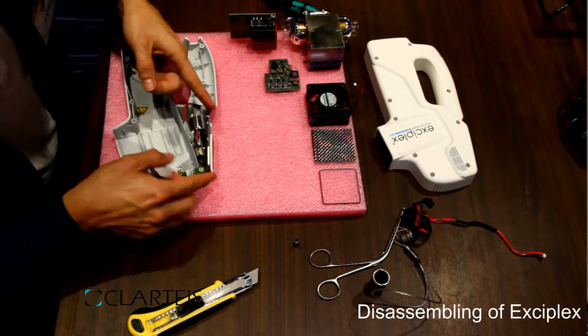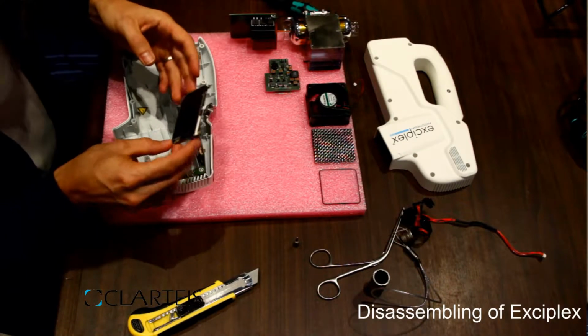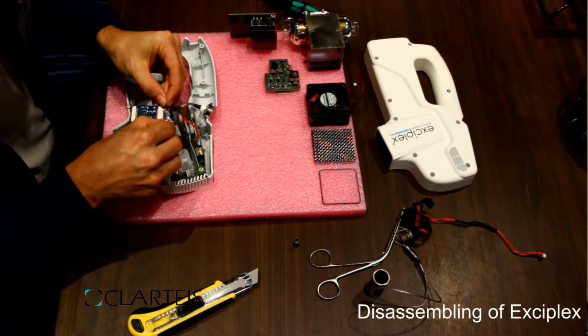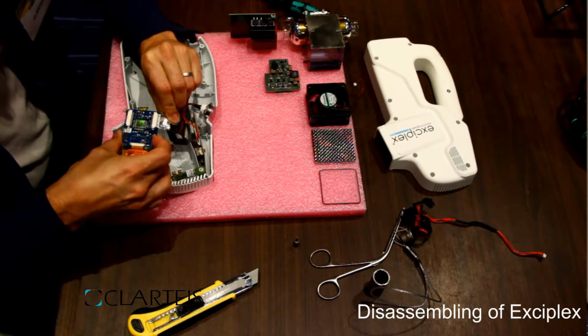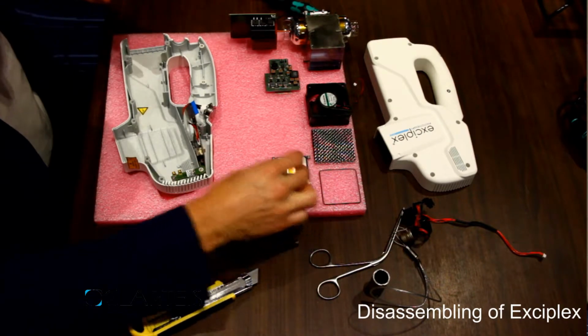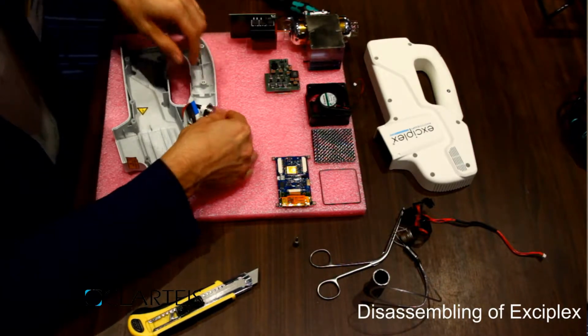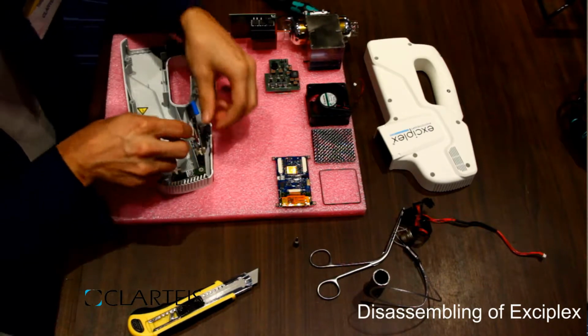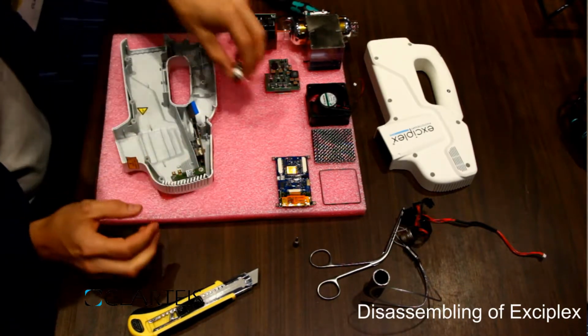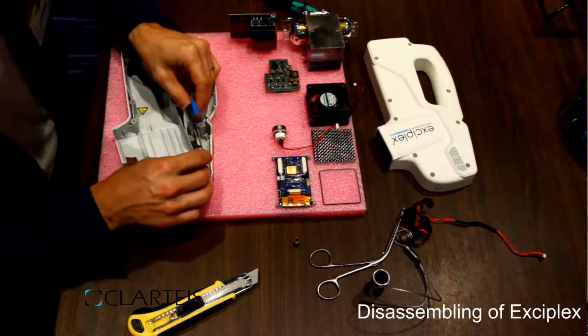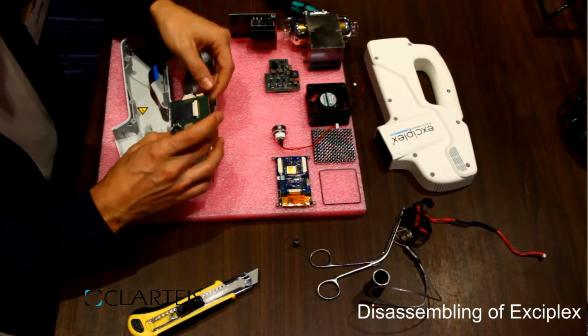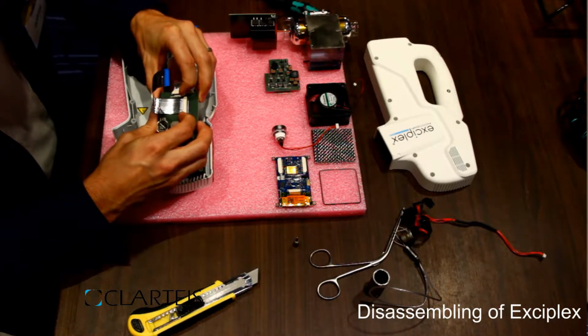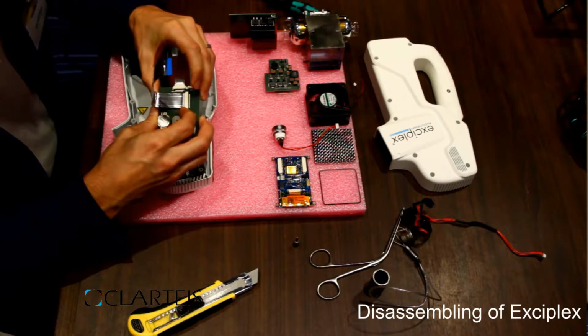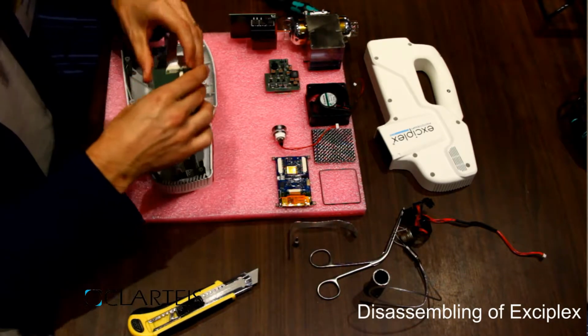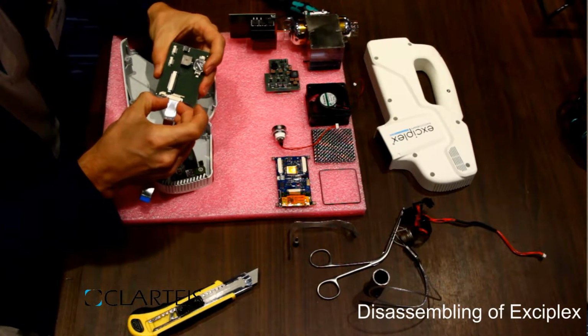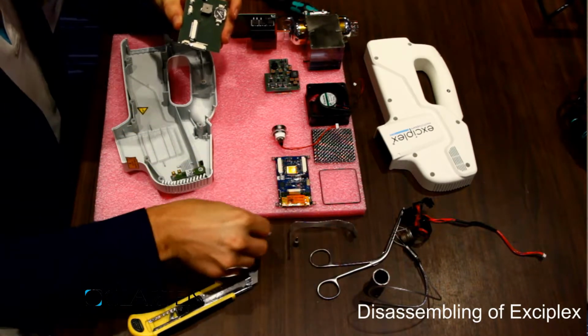Then you will have to remove the screen. So you move it up, turn it, and carefully unlock the connector to remove the flat cable. Now you have to remove the trigger, so unlock the nut, put it up and carefully disconnect this connector from the LVB board. Now you can slide up the LVB board, carefully unlock the connector of the display and remove the flat cable. The same with the power connector. Remove the cable.